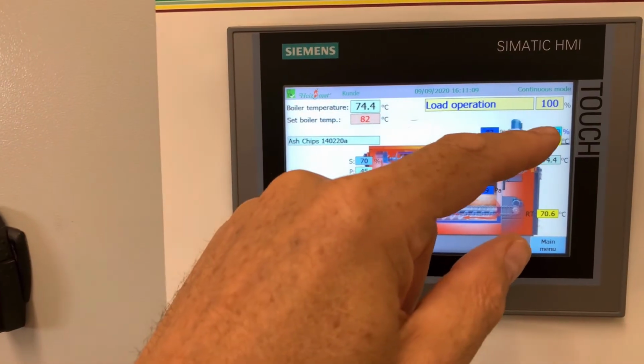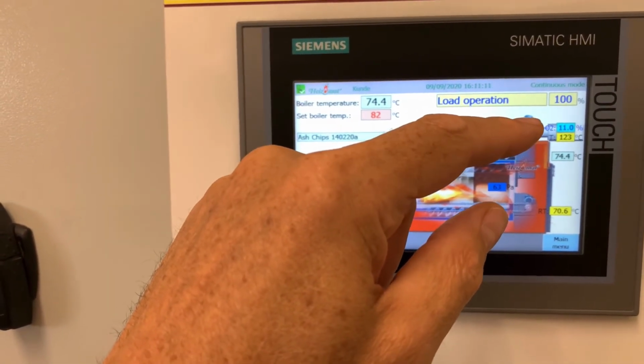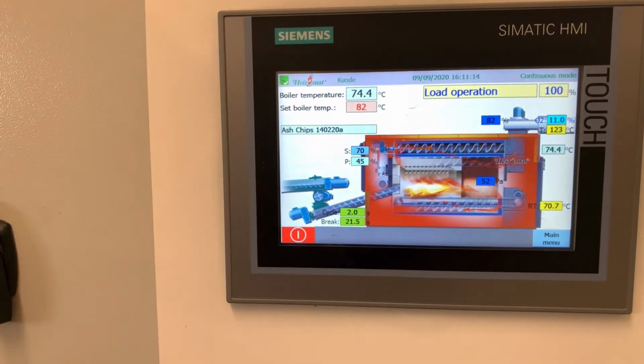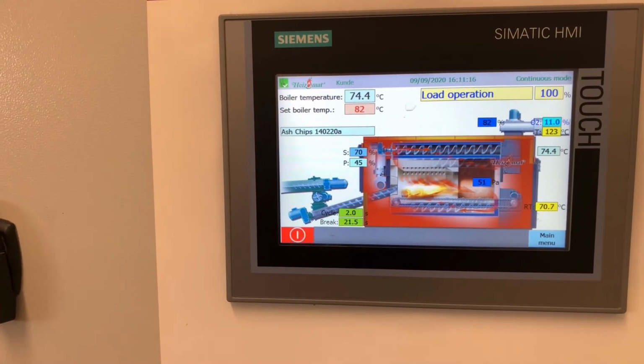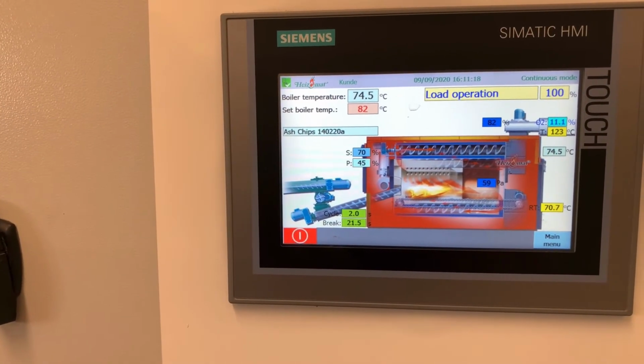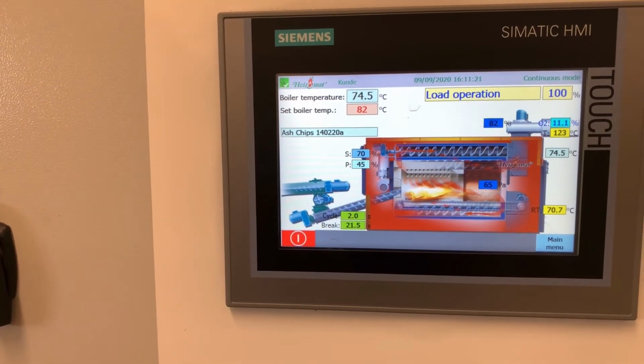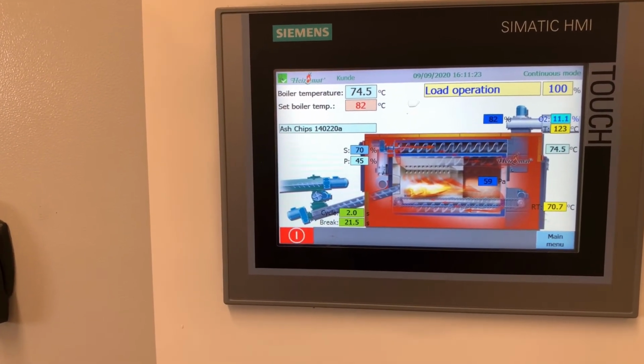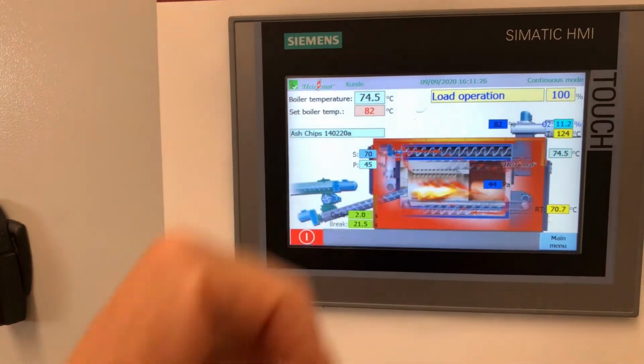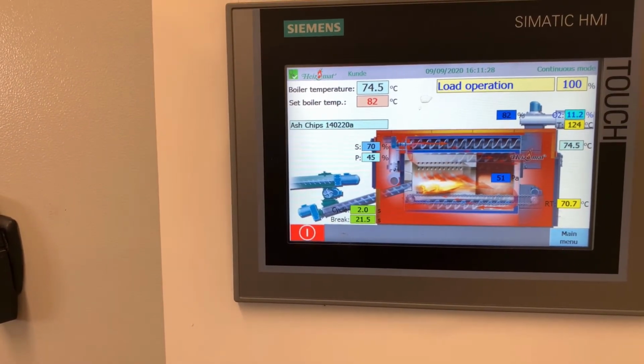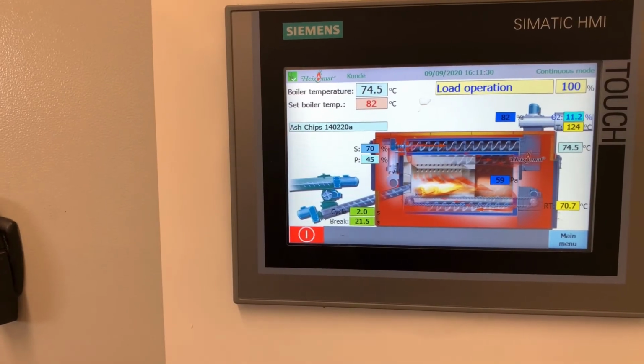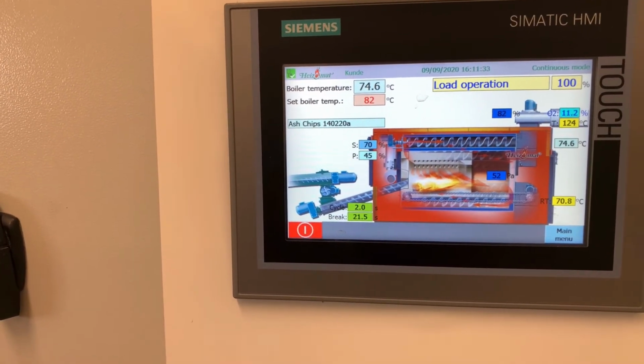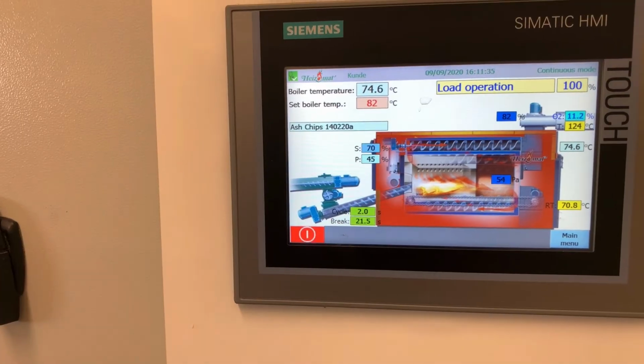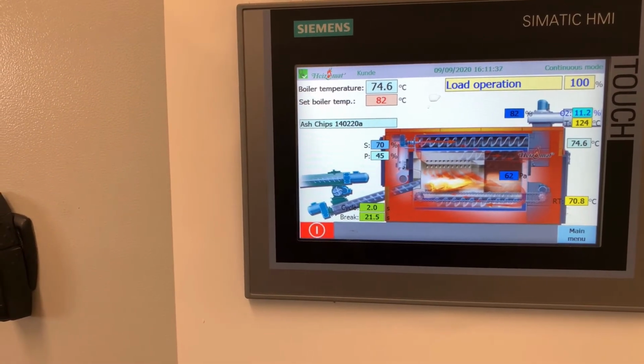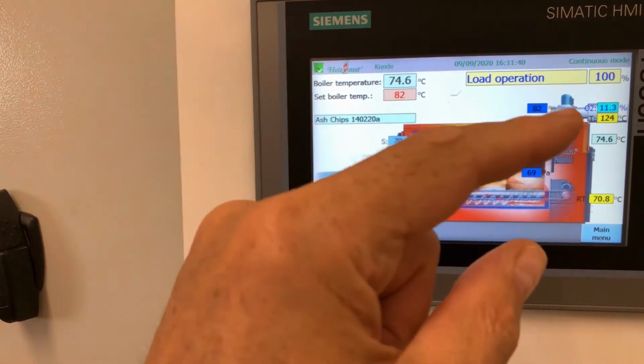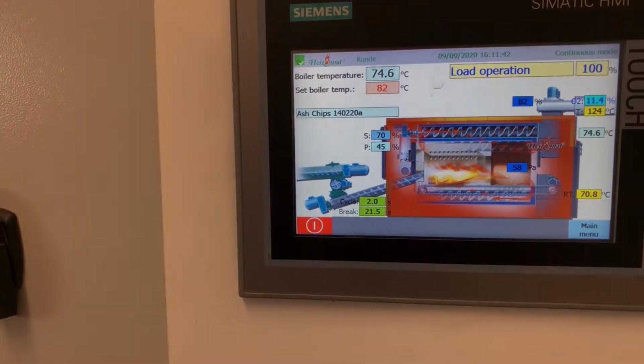Over here on the exhaust, the flue gas blower, you'll see that there's an O2 sensor, oxygen sensor. This is very much like in your car, and it's measuring the oxygen level. The ideal setting for us to be at the optimal efficiency is between 10 to 12%. You'll also see there the flue gas temperature. It's currently at 124 degrees Celsius. When the boiler's up to full operation and been running for a while, it will probably get up around the 150 degrees, 160 degrees Celsius. This tells us what our return temperature is and currently what the boiler supply temperature is.